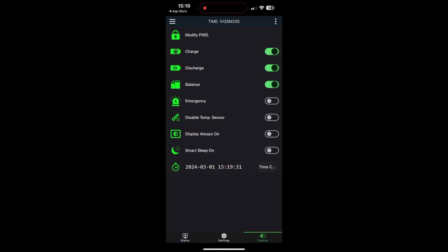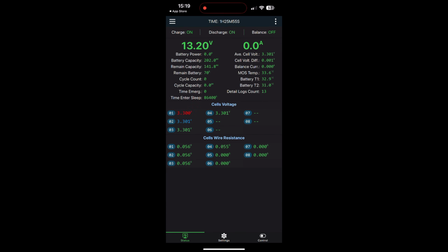Okay, we've got the time setting here. I've just calibrated the time to today, which is 1st of March 2024. So that's how you calibrate it. So in terms of the BMS, that's all the settings that you really need to know about. You can see now that up the top, the charge and discharge is on, the balance is off. The reason being is, even though the balance is on in the settings, the balance is off there because the variance between the cells is not more than 0.01, hence the balancer is not active, okay? And you can see now that the resistance of all the wires has come up as well.